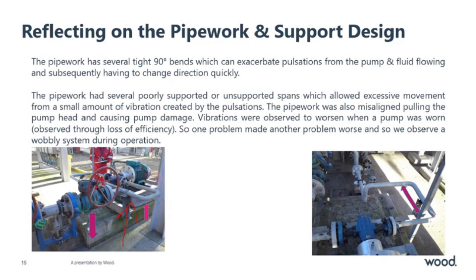You can also see some tight bends in the right hand photograph. So high velocity, pulsating fluid would hit a sharp 90 degree bend and then another and another and so on. So the recipe for disaster is starting to form before our eyes.